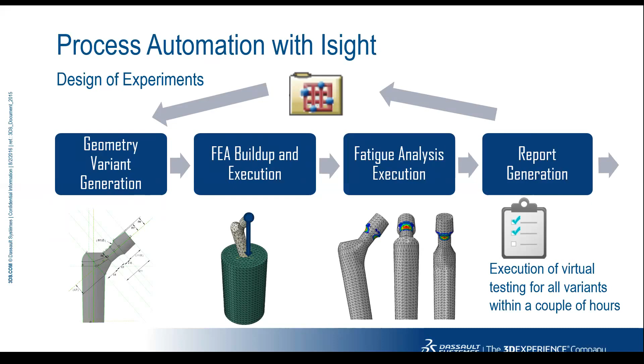So should we find that the design will not meet the certification criteria, we can use Tosca to locally optimize the geometry to improve the device performance. The objective here was to minimize the damage, focusing on the neck of the implant and considering relevant manufacturing constraints, because obviously we have to be able to manufacture this. And in this particular optimization case, fatigue life increased almost 5 times.